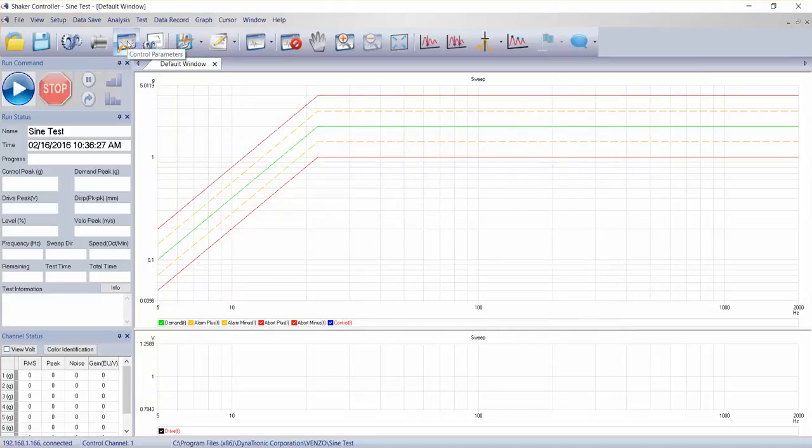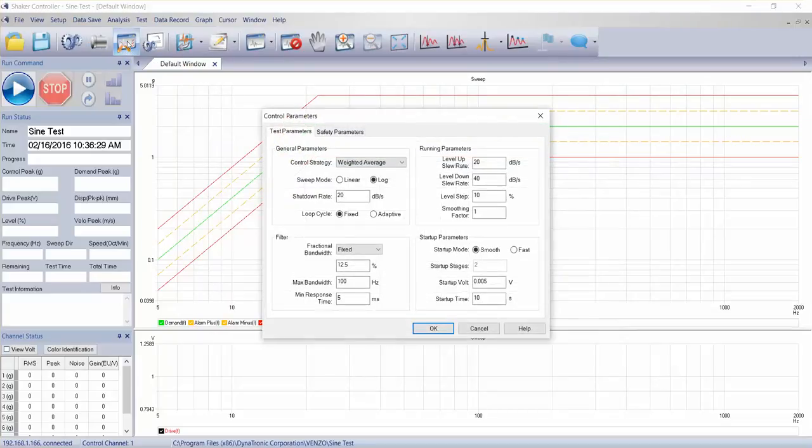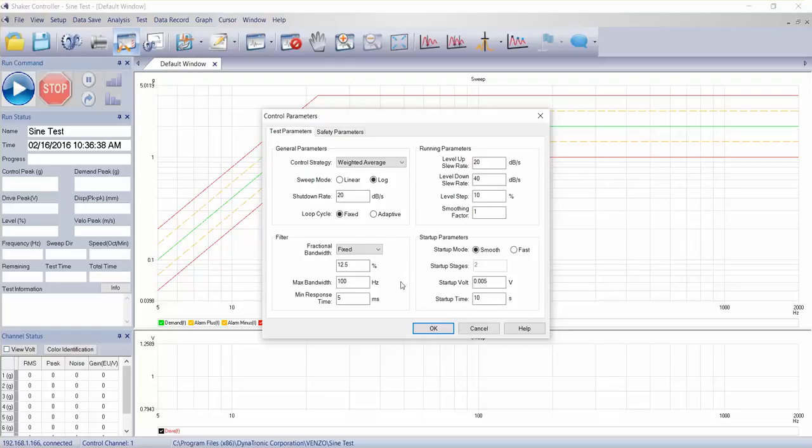We have the control parameters icon here, and similar to what we saw in random, we have some general parameters, some running parameters that we can set, the filters for the tracking filters, and some startup parameters dealing with the output voltages and the startup of the test.